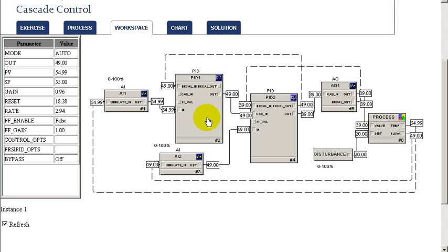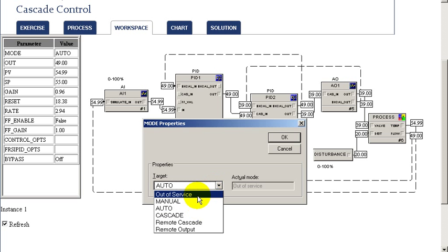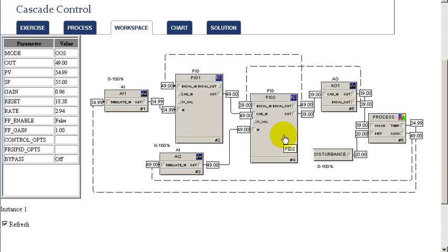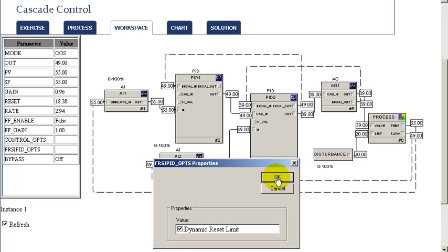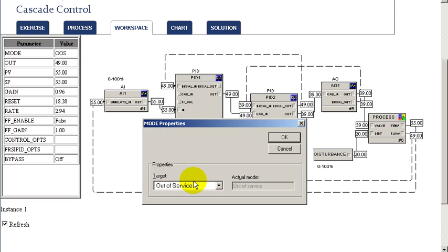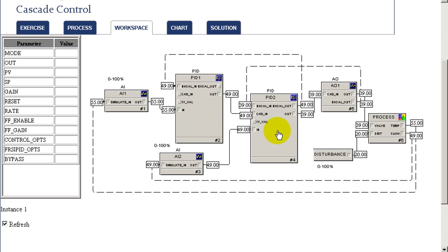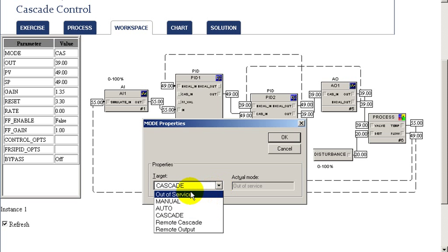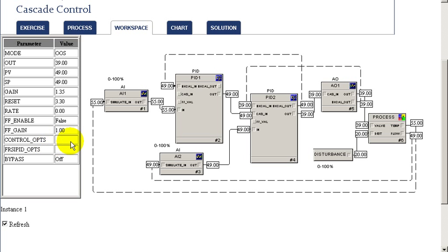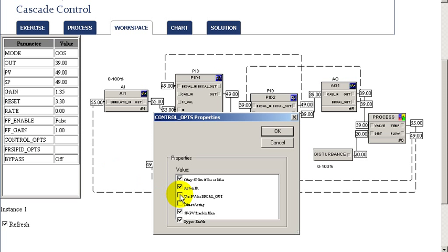That's one of the major benefits of cascade — to be able to take the disturbance with the inner loop and avoid it impacting the outer master loop. One of the things often provided in cascade control is dynamic reset. To enable dynamic reset, in this particular instance, we have to have the loop out of service. When we have it out of service, we can change and set dynamic reset to be enabled. After enabling dynamic reset, then in the slave loop, we need to set the control option to provide the PV as the back-cal out.